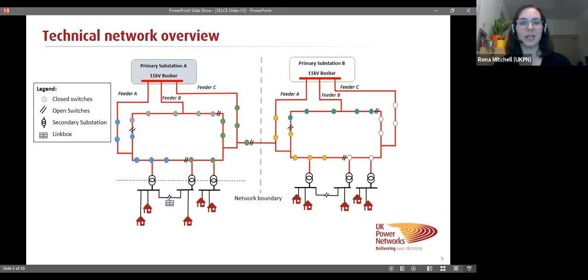What we see here on the screen is an approximation of how the energy network works. The houses where you are, down at the bottom of the slide, are all connecting at low voltage. Then as you go up the network, we have different feeder groups, and the ones that are all the same color are all together. So for example, if on the left, the homes in the neighborhood where the blue dots are all get a heat pump and electric vehicles, that could put some constraint on the cables in that area, so we would need to manage that.